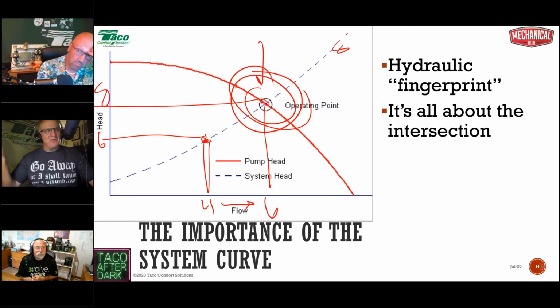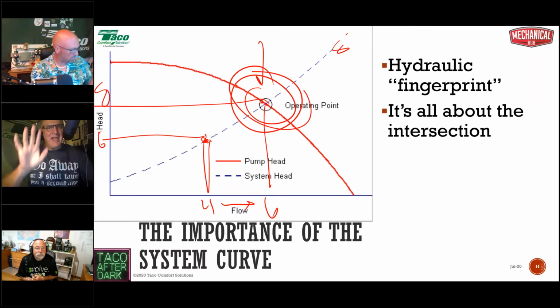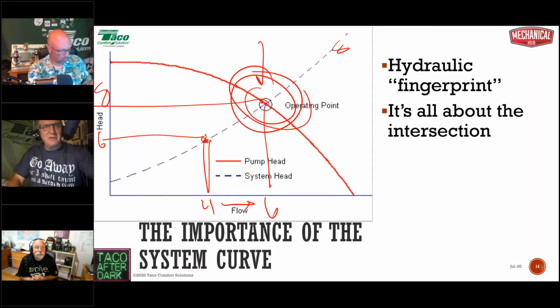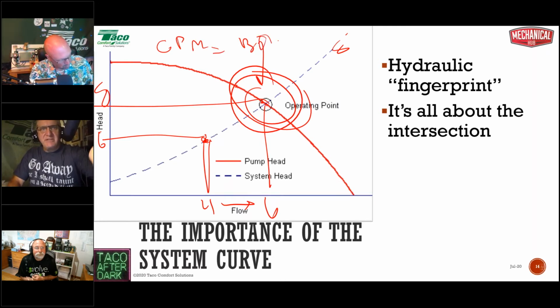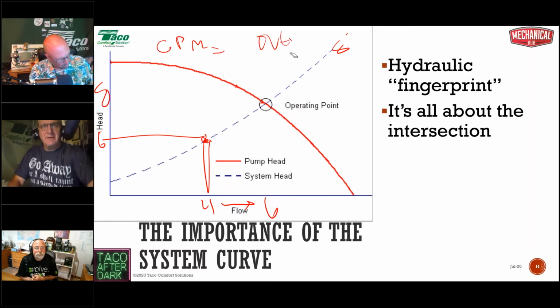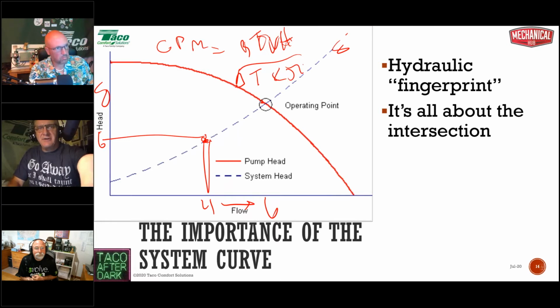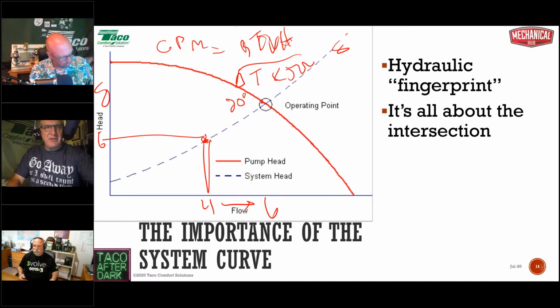Here's the thing, remember our universal hydronics formula. It states that GPM equals BTUH divided by delta T times 500, right? We go through a lot of math here to come up with our 20-degree delta T. That's our design, and we came up with 4 GPM, right? And that would be 40,000 BTUs under design conditions, coldest day of the year. Well, screw it.